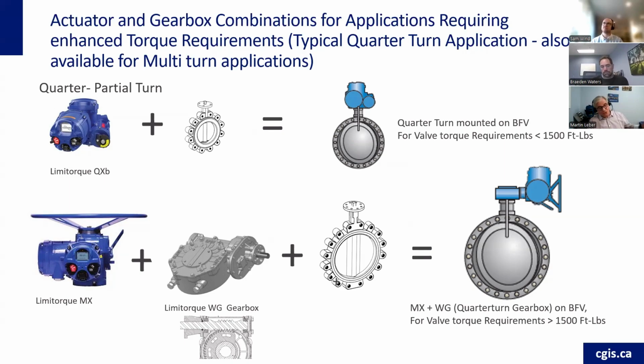Typically our quarter turn size QX goes up to 1,500 foot-pounds. Anything less than that with a factor of safety, you could direct mount it. Otherwise, you're looking at using a multi-turn with a quarter turn gearbox, and you could get very big torque values out of that combination. Likewise, for a multi-turn application, you could get a multi-turn gearbox with a multi-turn actuator and significantly increase your torque output.